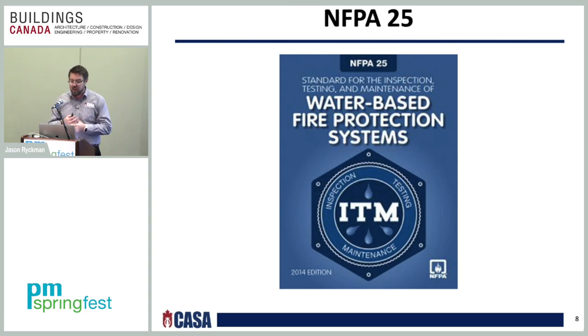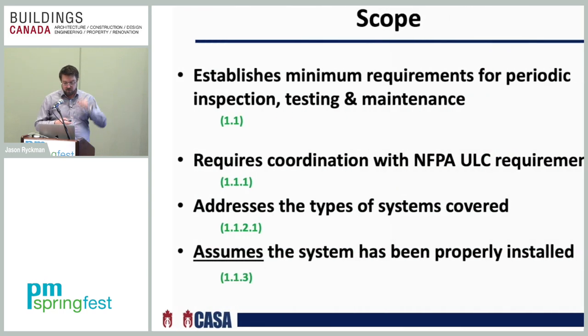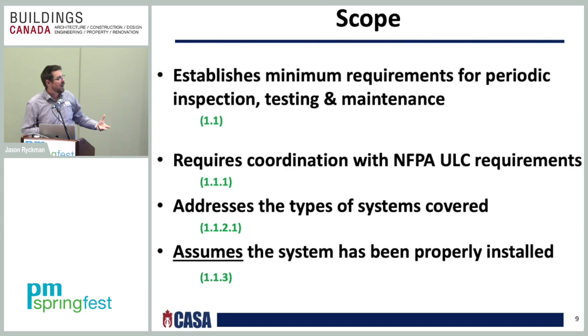Again, this document was actually, if you remember way back when, NFPA used to have a document that was an extension to NFPA 13A and NFPA 14A, which was a recommended practice for inspection, testing, and maintenance of systems back in the day, which basically were practices that were developed in New Zealand and Australia. So with the NFPA 25 document, and by the way, with CASA members, that's all we do is use the NFPA 25 document, just to make everyone aware of that.